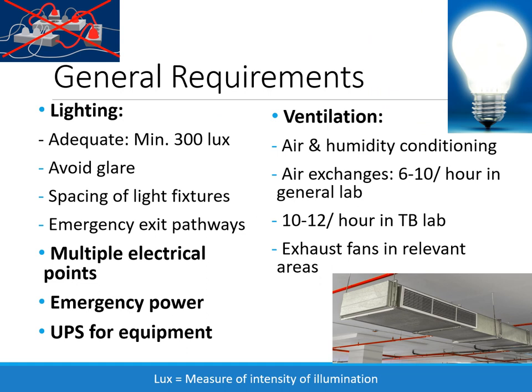Lighting: a laboratory must have a minimum lighting of 300 lux, where lux is a measure of intensity of illumination. The lights should not produce a glare on the workbench. There must be appropriate spacing between the light fixtures, and the emergency exit pathways must also be lit adequately.